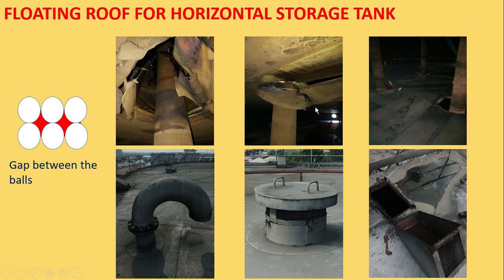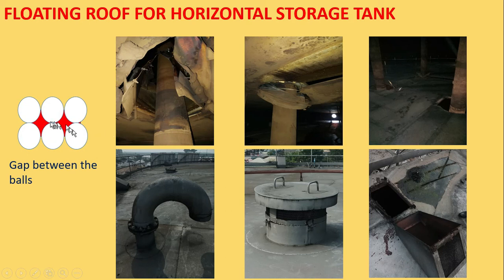But when we compared the results of this tank — with only 10 to 15% of PMS or gasoline exposed to air, plus an open atmospheric breather — the evaporation loss on this tank was quite low, even in comparison to a low-pressure gasoline tank. So with this example, it is proven that even with a restriction of the exposed area, evaporation loss gets reduced drastically.